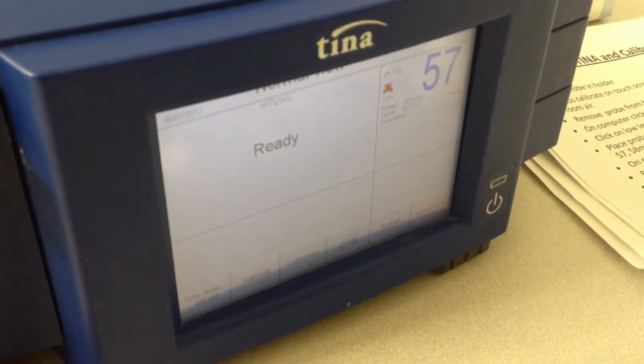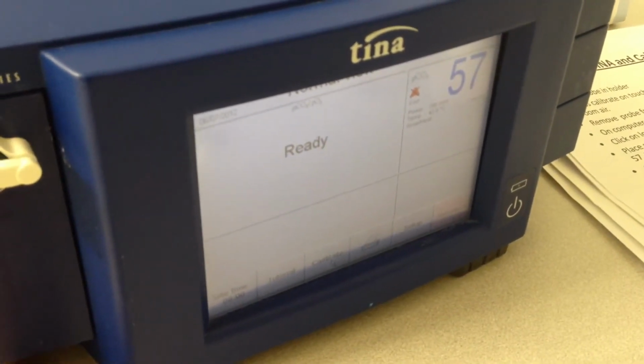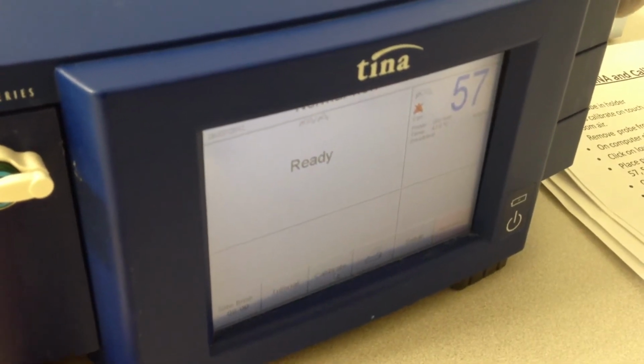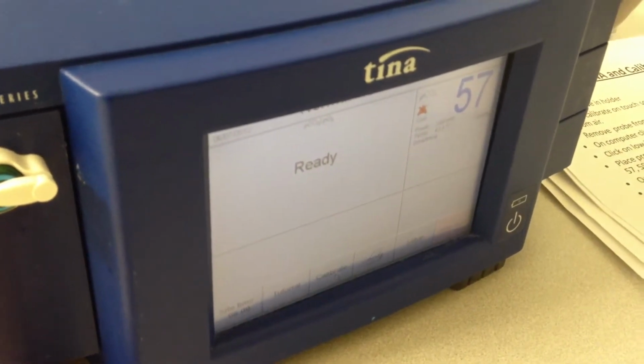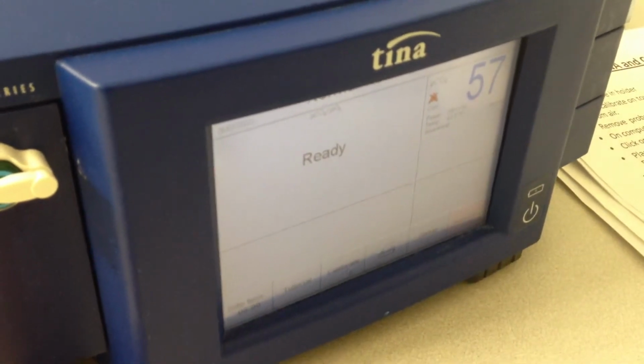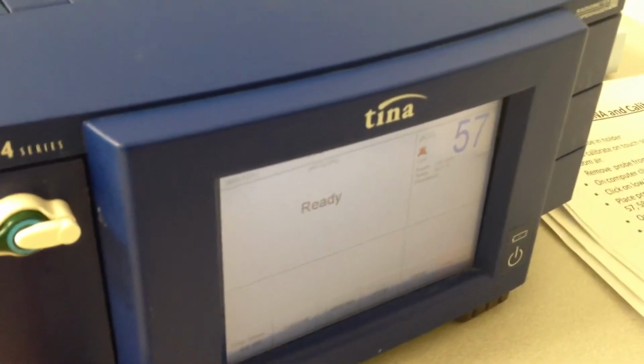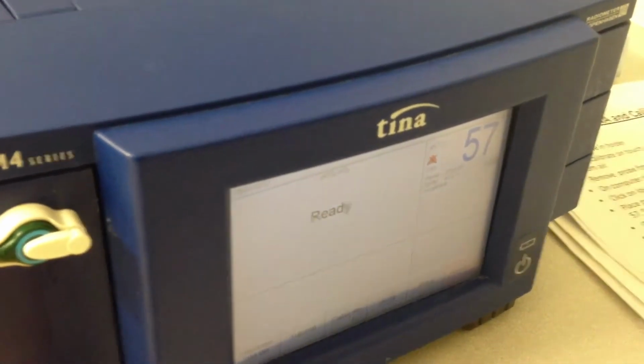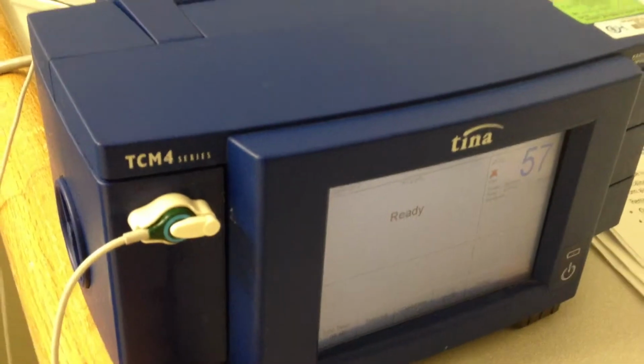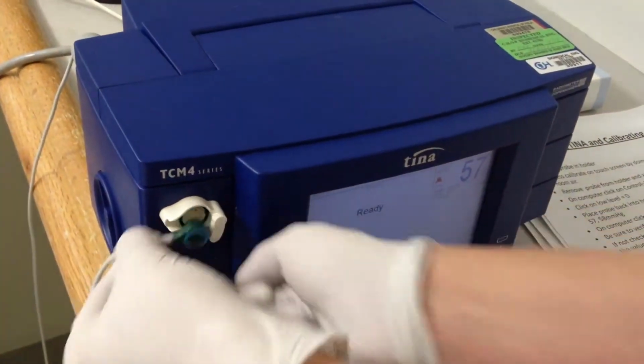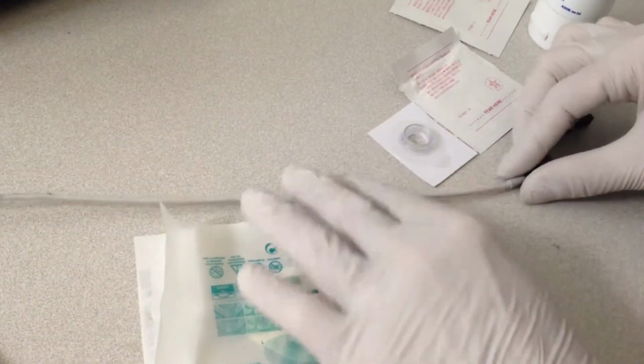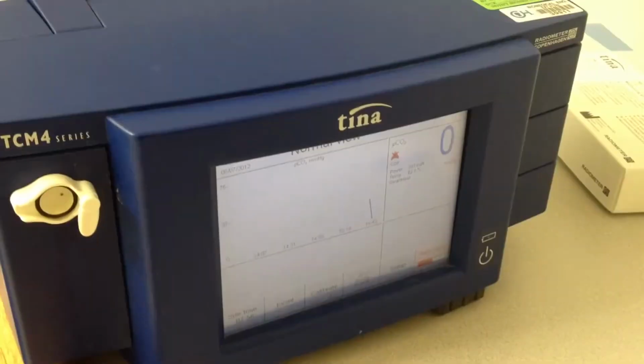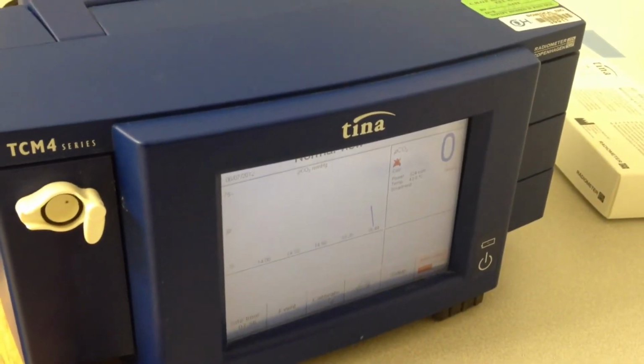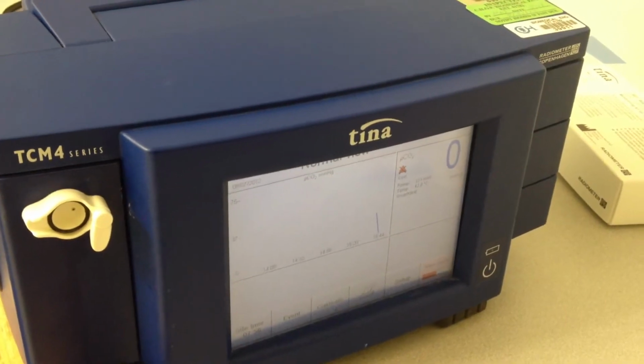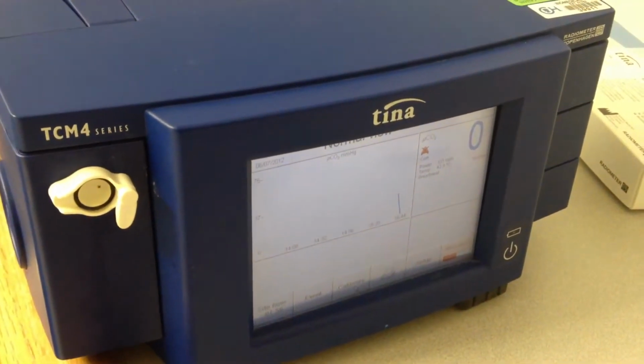Okay, so the machine is calibrated now, and that took approximately anywhere from 60 to 90 seconds to run through. And now we're at the touch screen and it's saying 57. So the next thing you want to do is remove the probe from the holder and allow the machine to read 0.